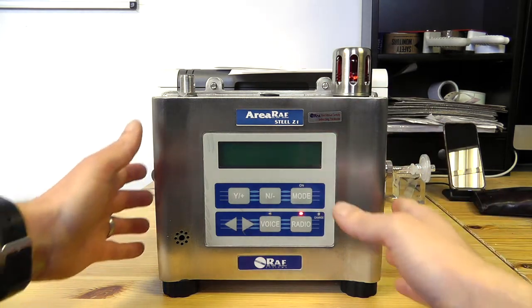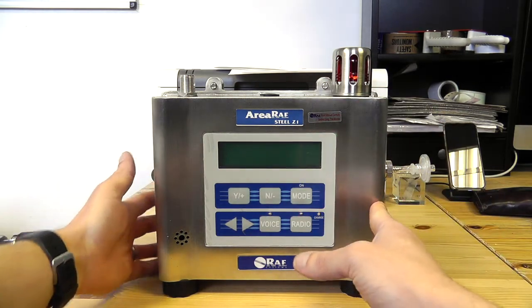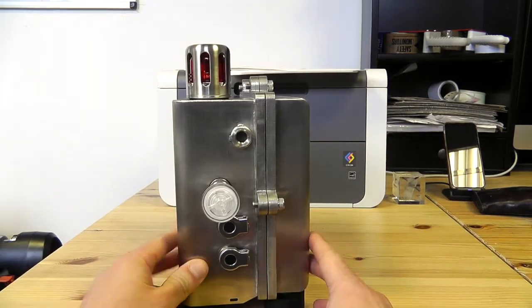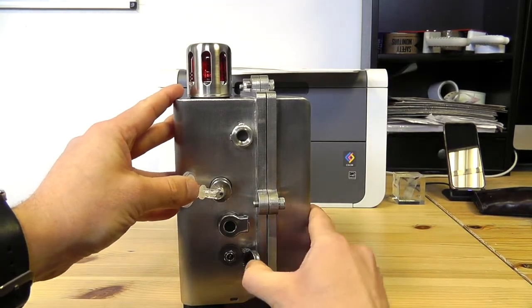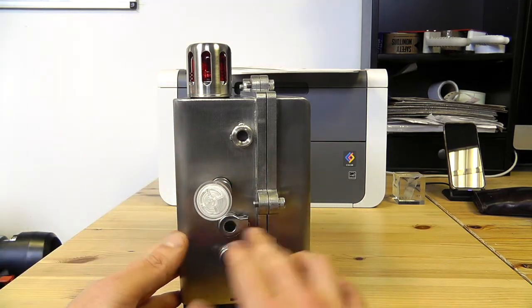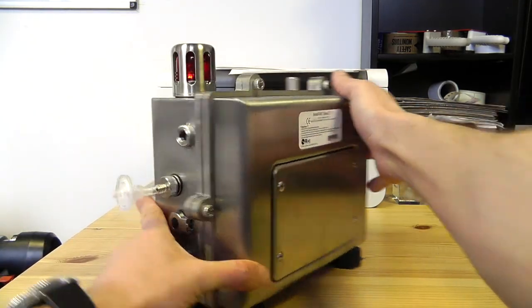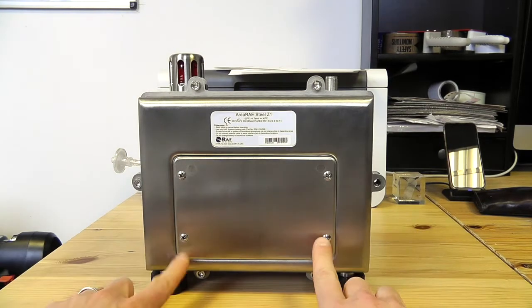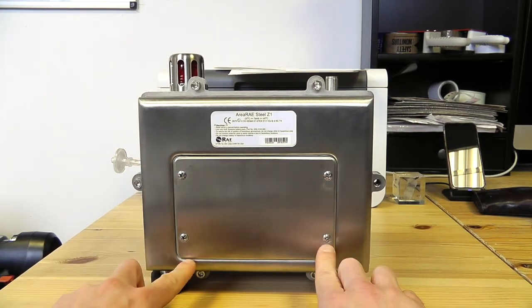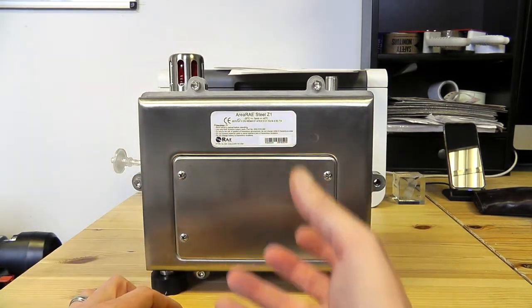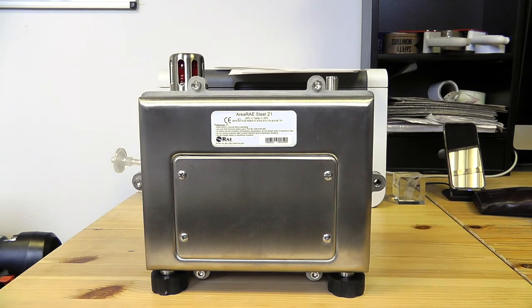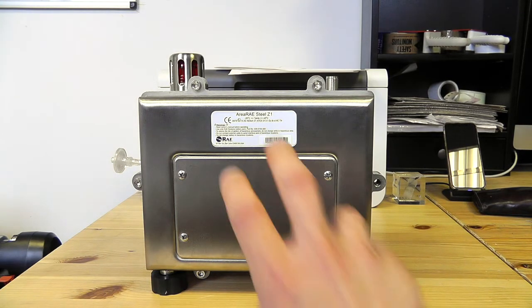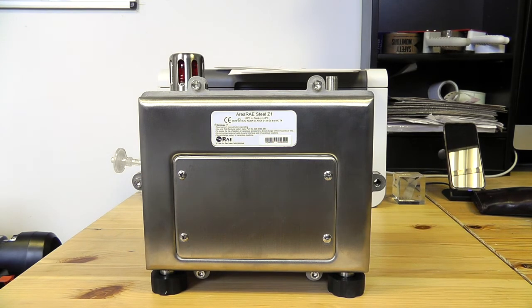Now we happen to have an ATEX Zone 1 AreaRAE Steel here, so that means there is no charging done via the side ports. On the Zone 2 derivatives, we've got capabilities for charging from the side ports, but on the Zone 1 instrument we don't. The battery packs are removed from the rear, so we'll undo these 4 screws, remove this section, and the battery pack pulls out, and we can put in a new separate battery which plugs straight into the instrument to alleviate any downtime on site.